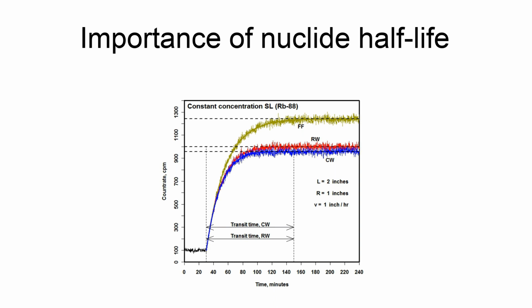The response of the monitor is sensitive to the half-life of the nuclide being collected and measured. It is useful to define a long-lived, LL, nuclide to have negligible decay during the measurement interval. On the other hand, if the decay cannot be ignored, the nuclide is considered short-lived, SL. In general, for the monitor response models discussed below, the LL response can be obtained from the SL response by taking limits of the SL equation as the decay constant approaches 0.